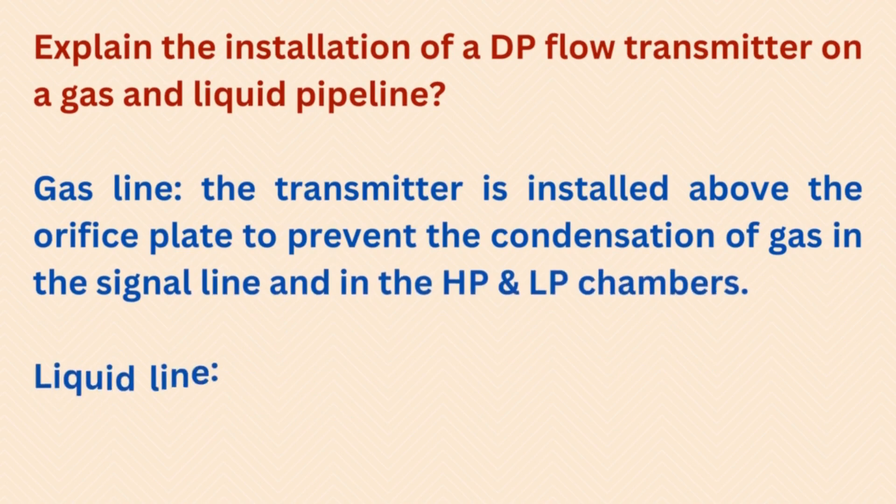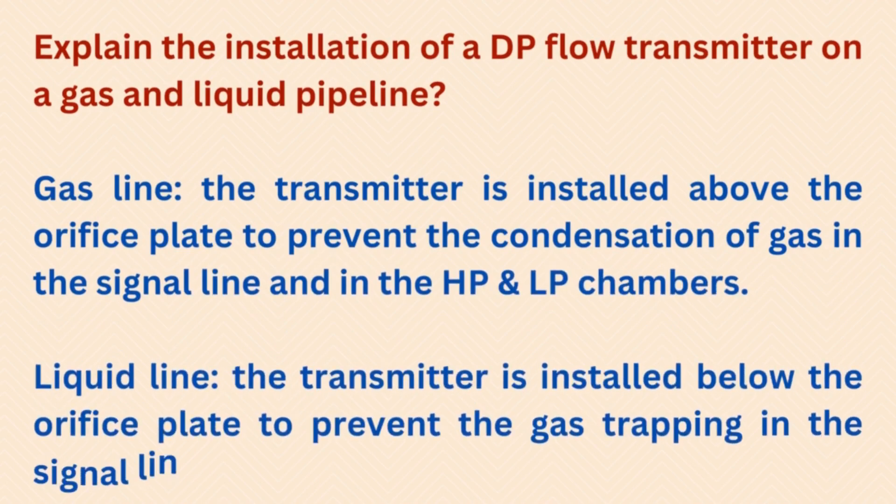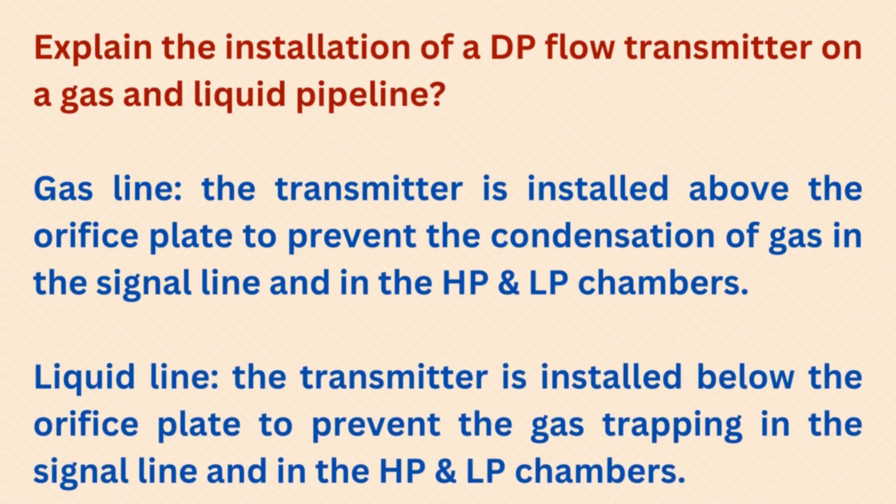Explain the installation of a DP flow transmitter on a gas and liquid pipeline. Gas line: the transmitter is installed above the orifice plate to prevent condensation of gas in the signal line and in the HP and LP chambers. Liquid line: the transmitter is installed below the orifice plate to prevent gas trapping in the signal line and in the HP and LP chambers.